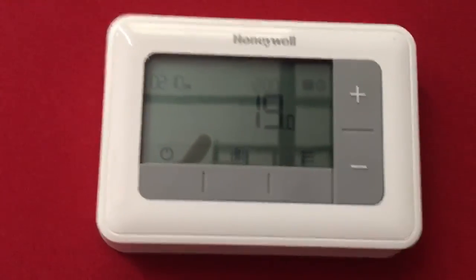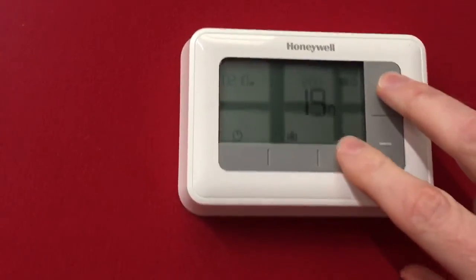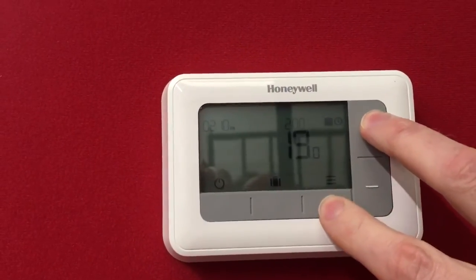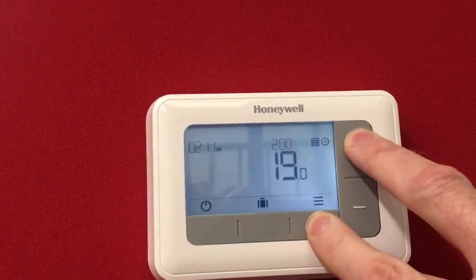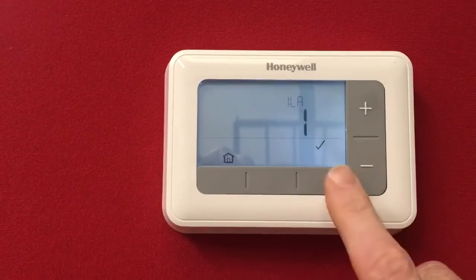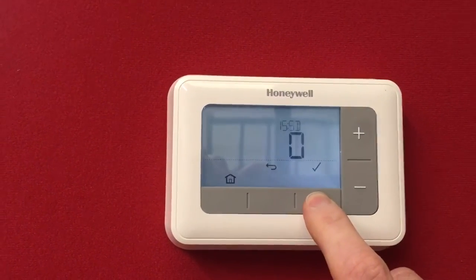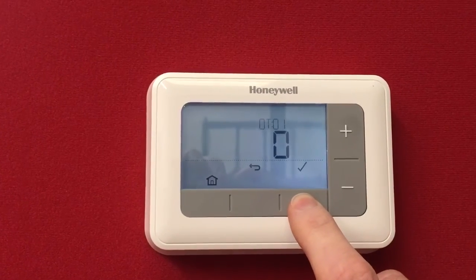So on the T4M, if you press and hold those two buttons together there, you get inside the installation menu. So what you have to do, you have to keep pressing the tick all the way down until you get past setting number 16, and then you come into the open therm controls.